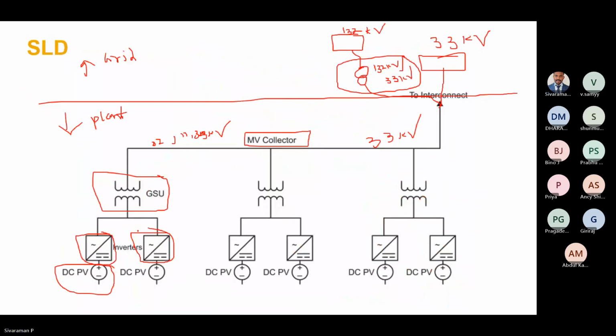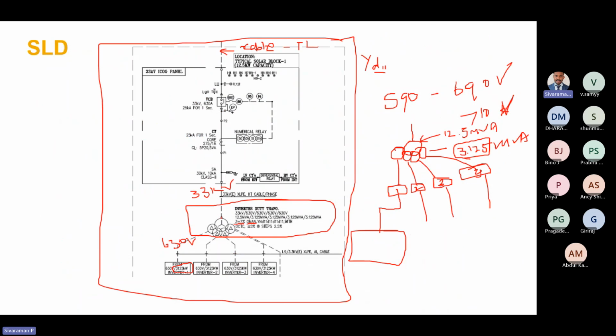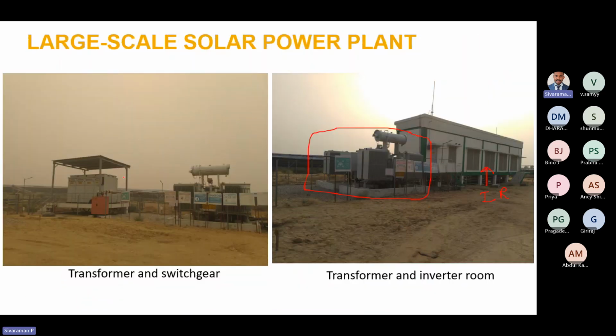In this example, this is an inverter duty transformer. Inverters are here, and after the inverter duty transformer there is a switchgear. This is a switchgear, 33 kV VCB. This is an outdoor type. They have provided one set also for that. The inverter duty transformer output will go into this switchgear, and after that it will go to the substation. Okay, some things I would like to inform you.